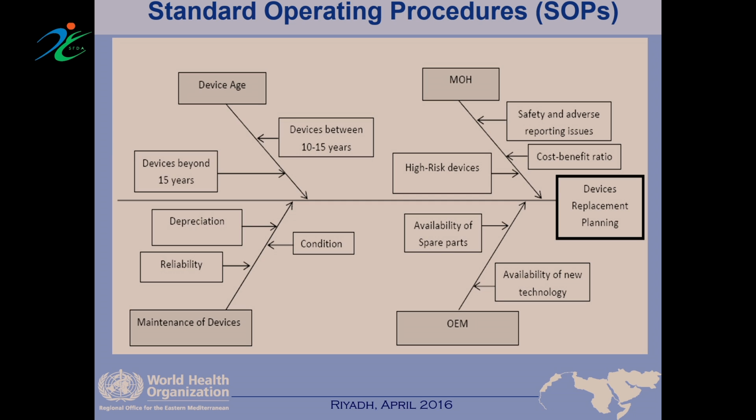So always think about what is the cost-benefit ratio. If I'm having equipment running but the breakdown is too high, then I have to look at how much I'm paying for that kind of repair. Definitely, if you don't have a system in place, like the CMMS, the Computerized Maintenance Management System, you're not able to tackle all those issues, because then you have everything on paper, and sometimes those papers are misplaced, so you're not able to catch that information.